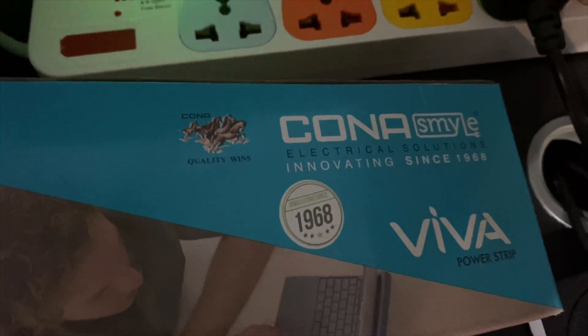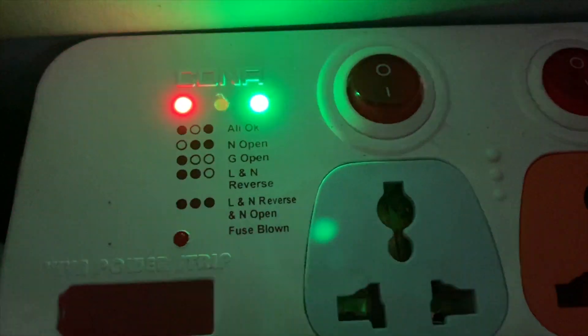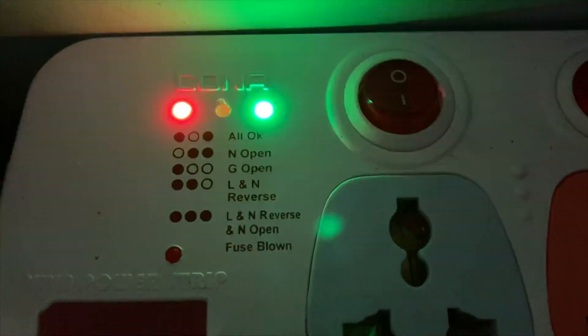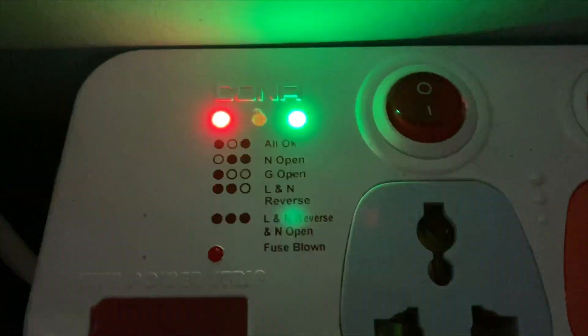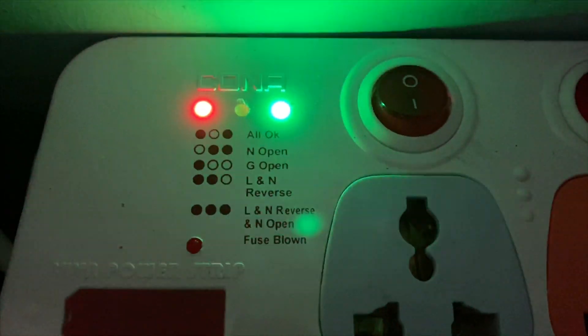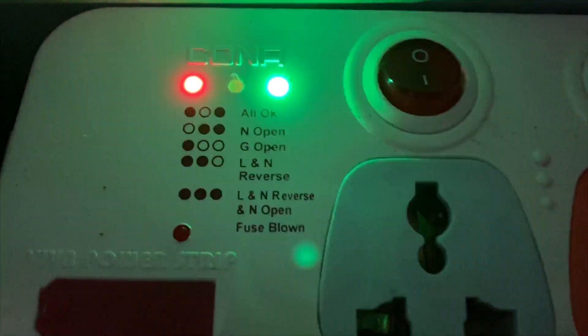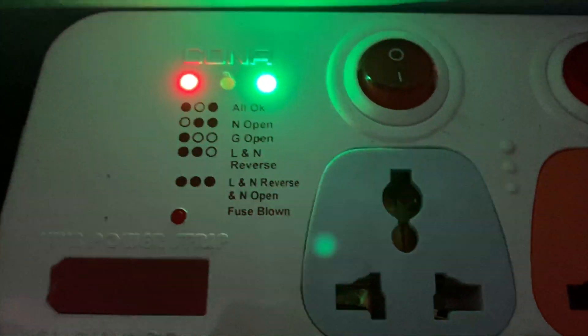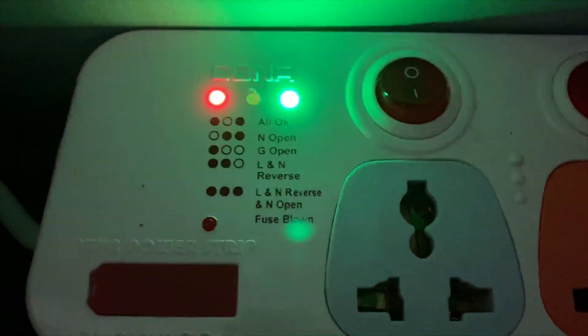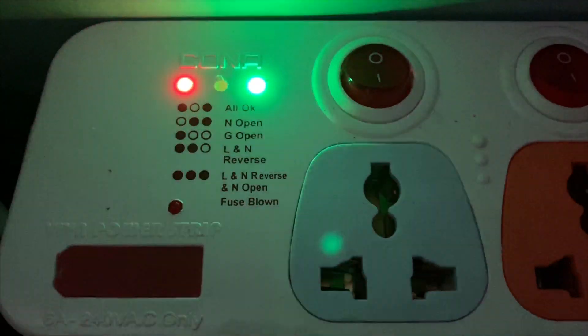I'm talking about this spike buster with extension cord, which is from Cona. It has three LEDs — red, amber, and green. When red and green are glowing, everything is okay. If the neutral is open, amber and green glow. If the ground (earth) is open, only red glows. If the line and neutral are reversed, red and amber glow. If line and neutral are reversed and neutral is also open, all three LEDs glow. The safest operating condition is red and green glowing, which indicates earthing is intact.